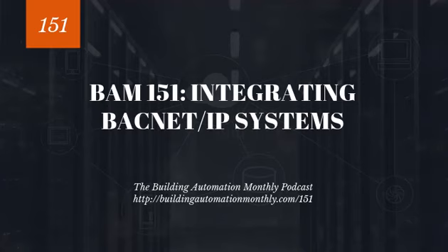And once those broadcasts are shared, each device on that network needs to have a unique device ID as well as a unique IP address. That device ID and IP address will form the BACnet ID for that IP device. And then and only then can messages be sent. Broadcast messages, as I said, are sent for Who-Is, I-Am. Unicast messages are sent for the different services. So we want to make sure that we get all of that set up.